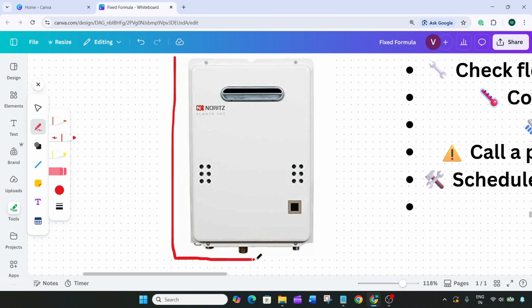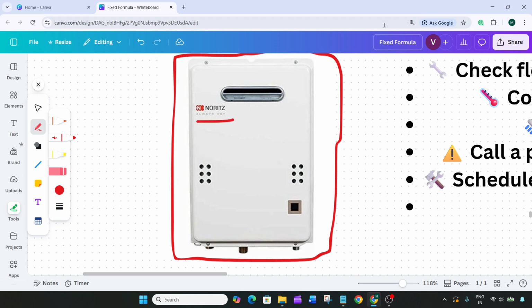First is the flow sensor. This part detects water movement and tells the unit to ignite. If your flow rate drops below about 0.5 gallons per minute, or the sensor is dirty or faulty, the heater won't activate.